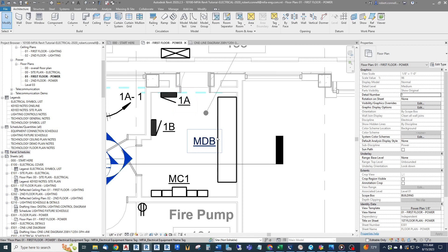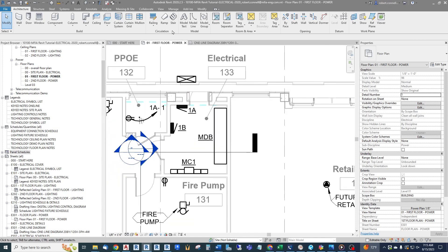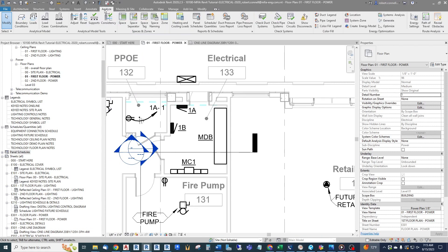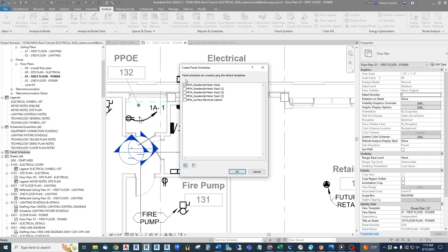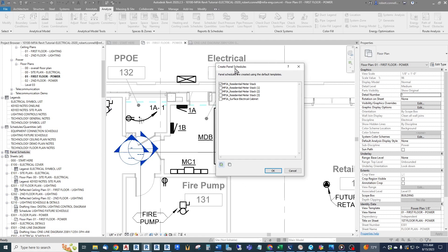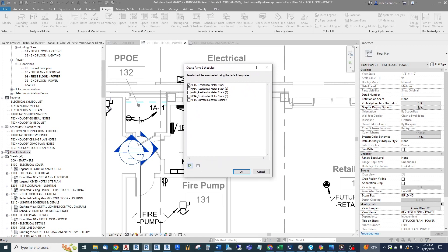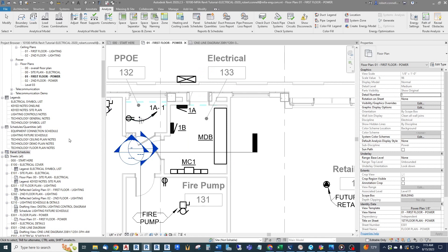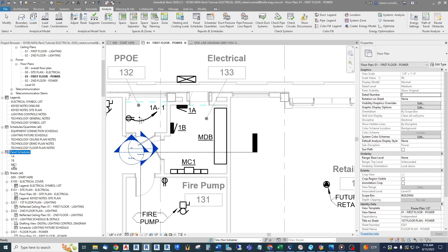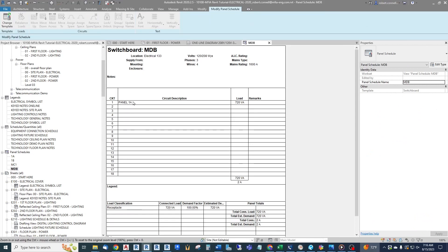That's as simple as that — panel 1A is connected to MDB. If you haven't created panel schedules yet, go to the Analyze tab and find Panel Schedules. Any panels not yet scheduled will appear in the list. Over at panel schedules I already have panel 1A, 1B, MC1, and MDB created. Looking at the MDB schedule, you can see panel 1A connected — the circuit description I typed in — and it brings in the loads that were on panel 1A. It also classifies the connected panel loads down below and applies demand factors.